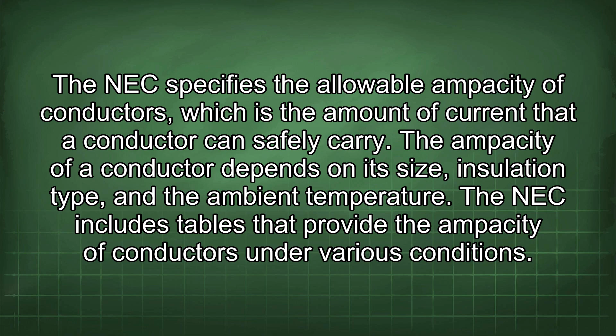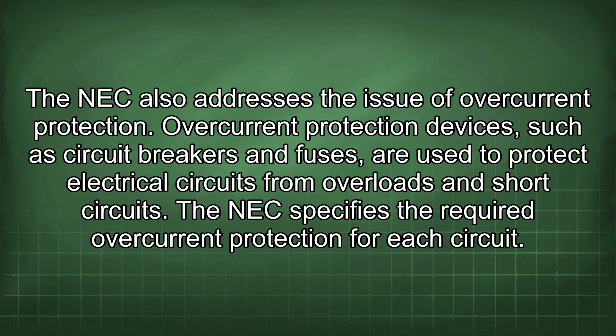The NEC also addresses the issue of overcurrent protection. Overcurrent protection devices, such as circuit breakers and fuses, are used to protect electrical circuits from overloads and short circuits. The NEC specifies the required overcurrent protection for each circuit. The size of the overcurrent protection device must be matched to the ampacity of the conductors in the circuit.